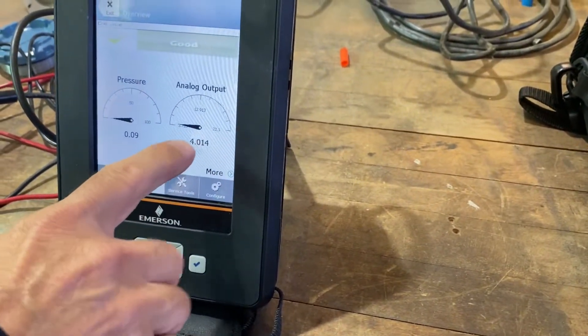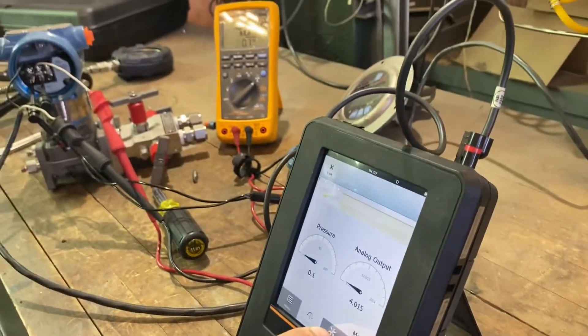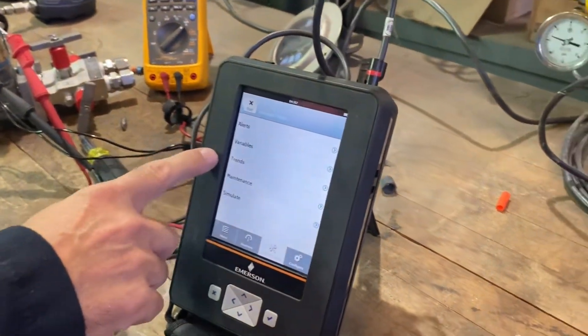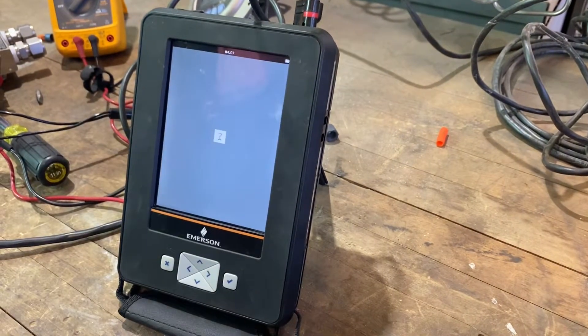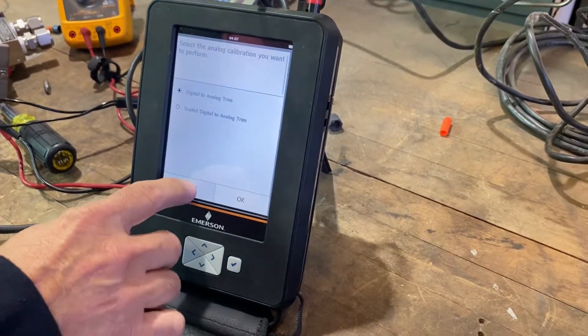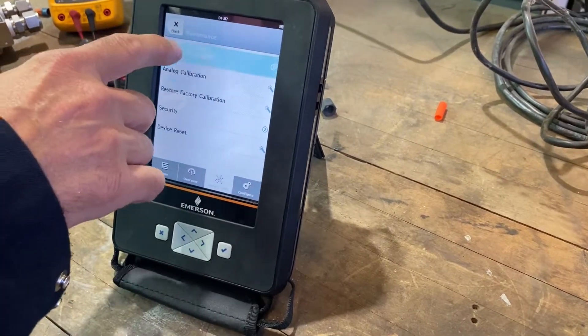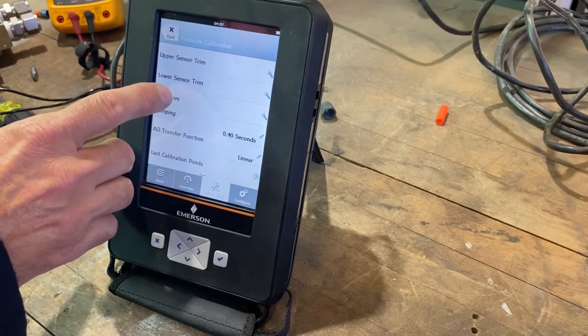So, it's connected on. It's reading what the meter is reading. Then, you want to go to service tools. Maintenance. Analog calibration. Actually, pressure calibration. Zero trim. Okay.